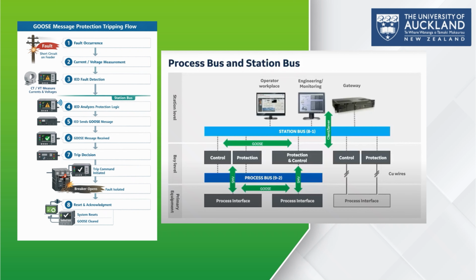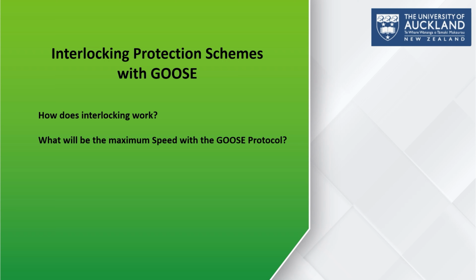So another question is, how does interlocking work? When a fault occurs on the busbar, the interconnected relays quickly coordinate, causing the relays of the incoming feeder to block the relays of the outgoing feeder and then trip the circuit breaker of the incoming feeder. The same happens vice versa when a fault arises on an outgoing feeder and the relays of the incoming feeder are prohibited to act. Since the GOOSE messages are sent relay to relay through an Ethernet LAN, there is no additional delay from intermediate equipment such as input filters or auxiliary relays, so the blocking signals can be sent faster than in traditional hardwired interlocking schemes. Peer-to-peer communication allows blocking signals to be sent to all relays at once, making the total operating time independent from the network size, complexity, or topology, right?